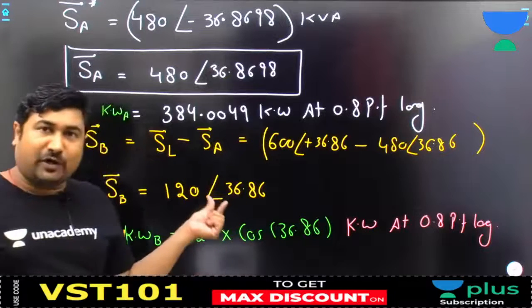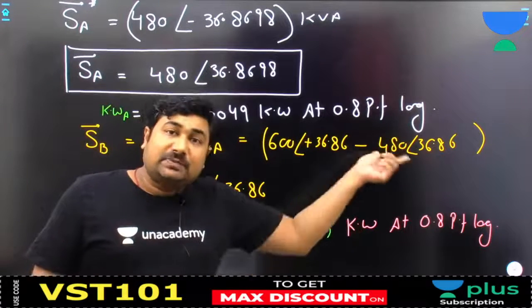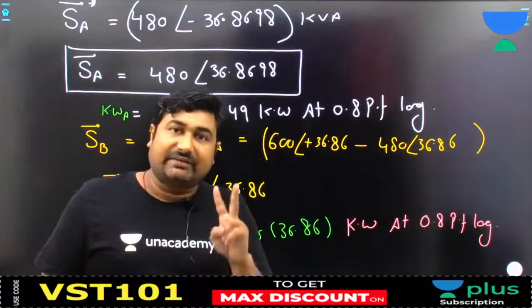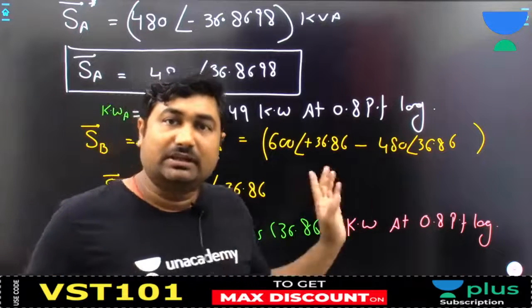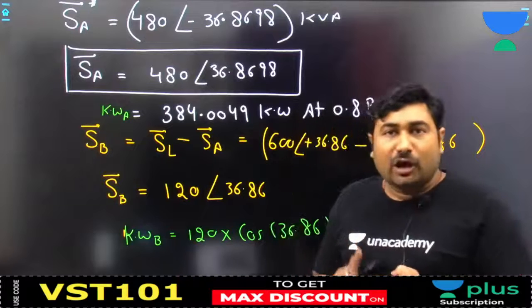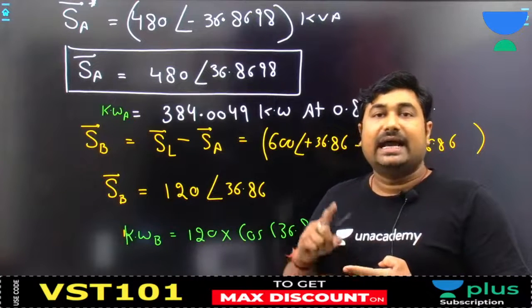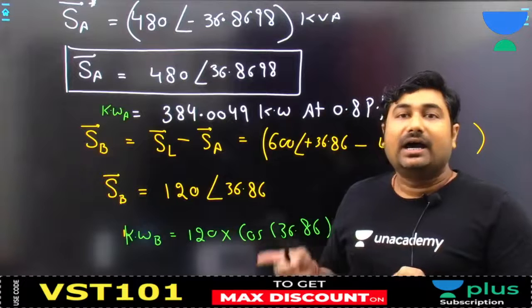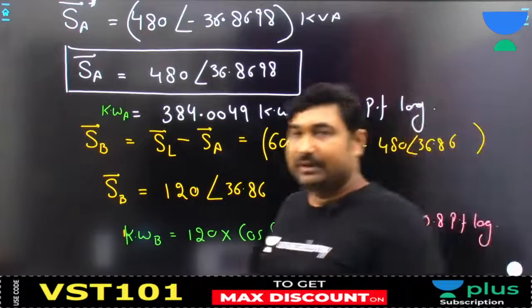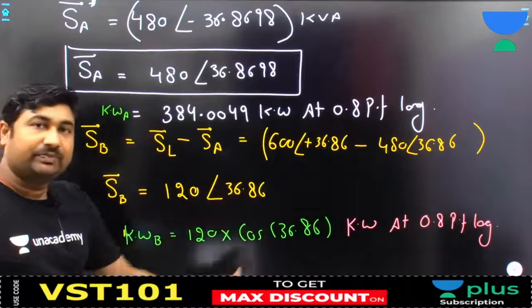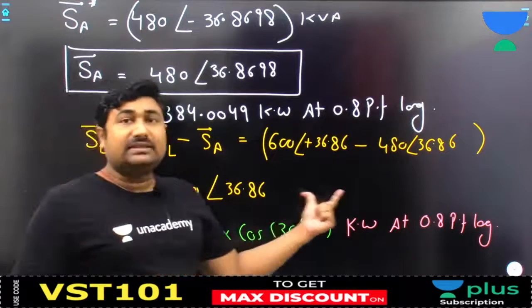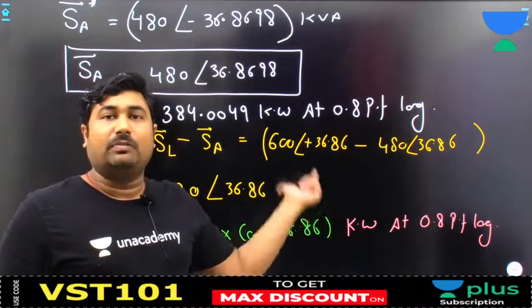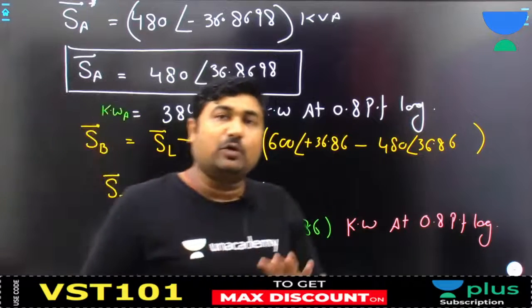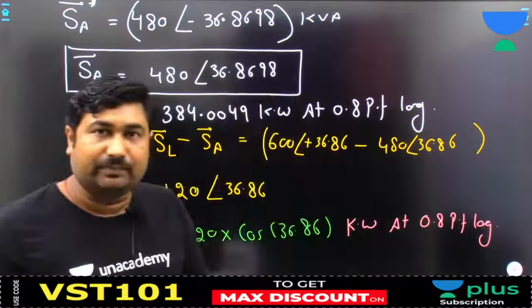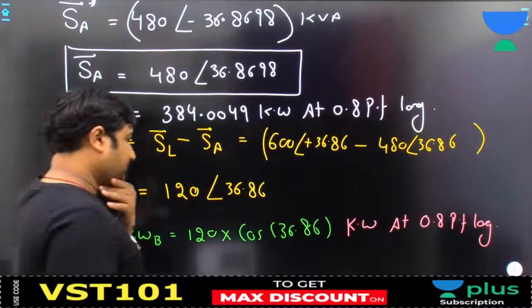So if the two transformers have the same X by R ratio, then both transformers will operate at the same power factor, same as the load power factor, under parallel operation. Now please observe, come to the next part. Up to this everything is okay. I am interested to know what is the maximum kVA that this combination can feed without overloading either of the two transformers.